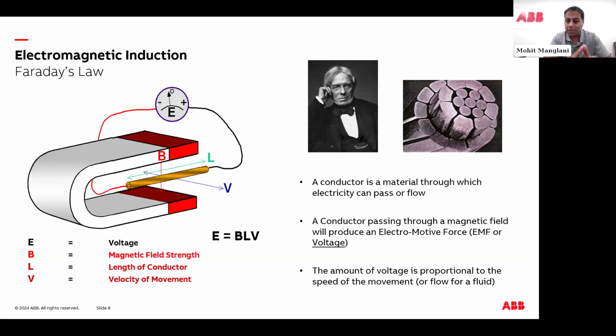So mag meter, what is it? A mag meter is a spool piece. It's a flow meter. You mount it in line, and you're able to get a flow rate based off the process that's there. Obviously, there's a few things that are required to make it work. It works on the principle of Faraday's law. The idea is that if I throw a conductive liquid through a magnetic field, I can generate a voltage, and that voltage is directly proportional to the flow. It's a very simple concept. Regardless of whether it's ABB's meter or anybody's mag meter, the concept is still the same in terms of basic functionality at the element level.